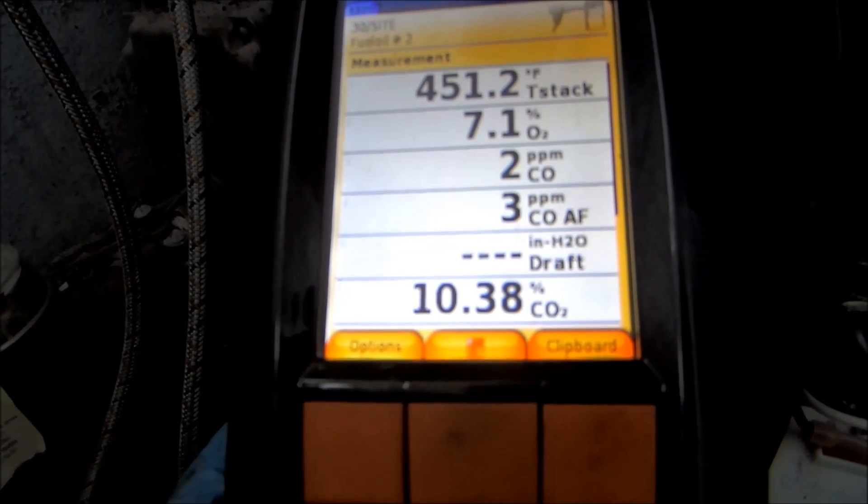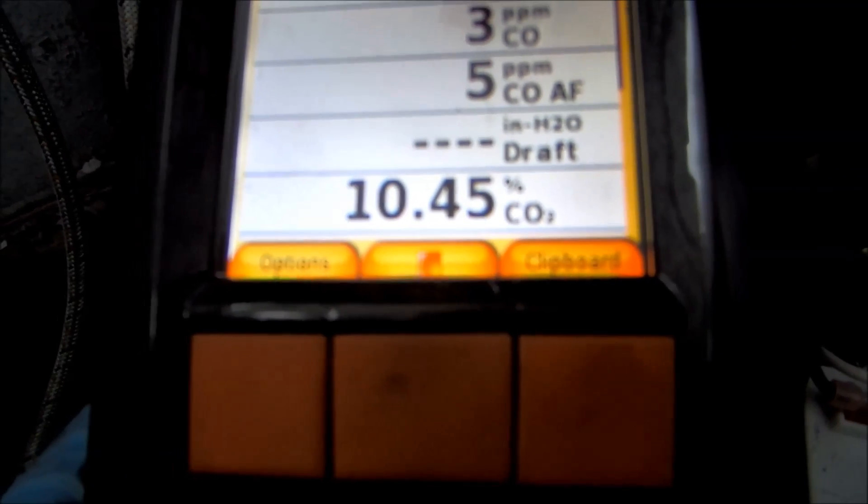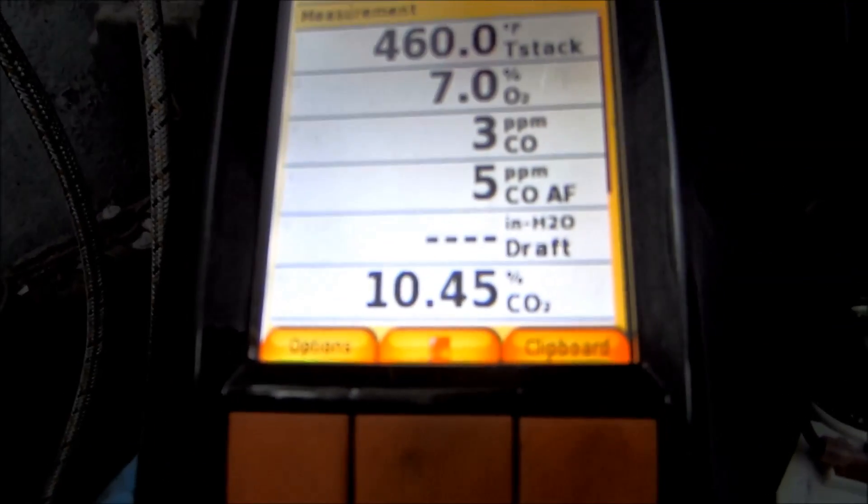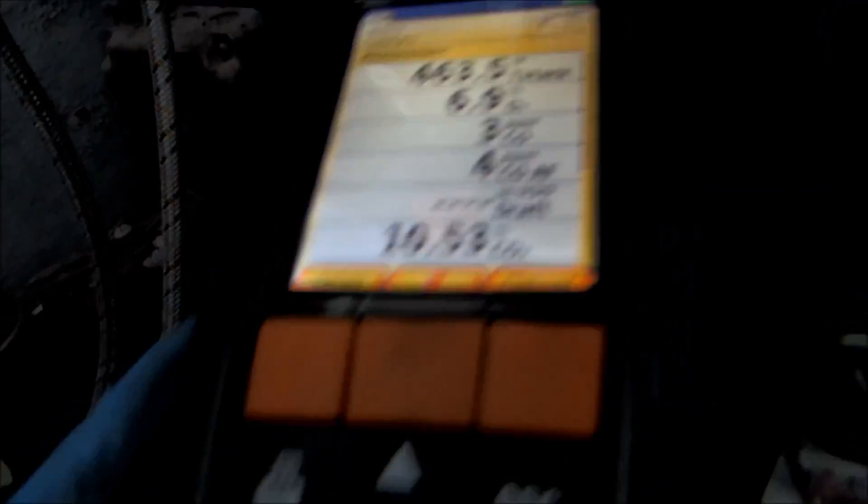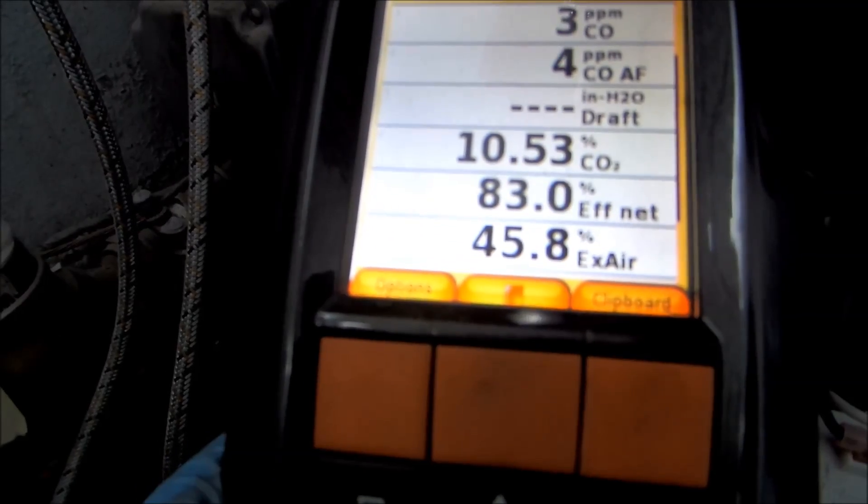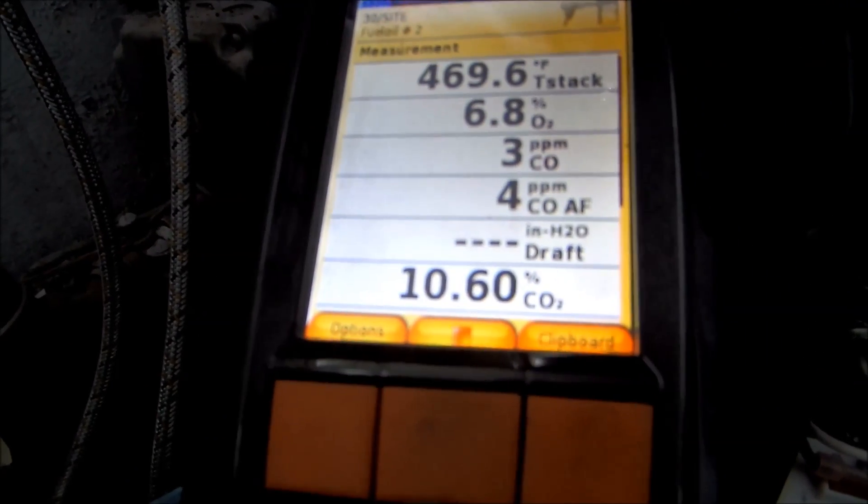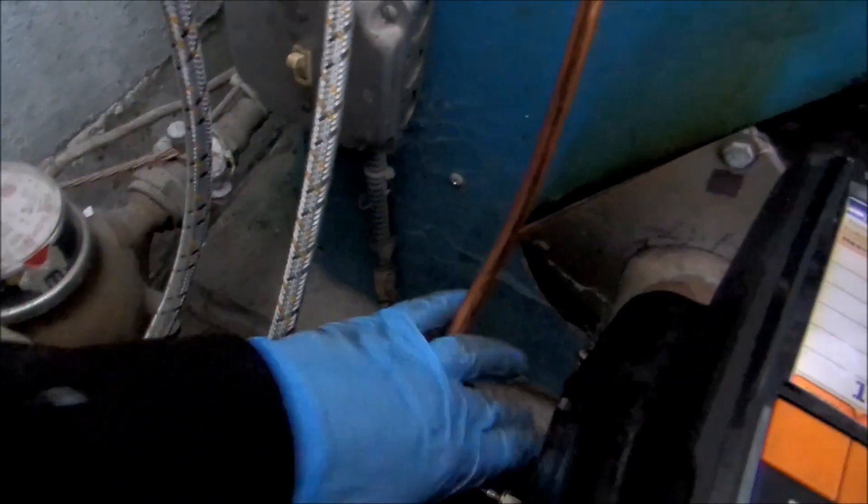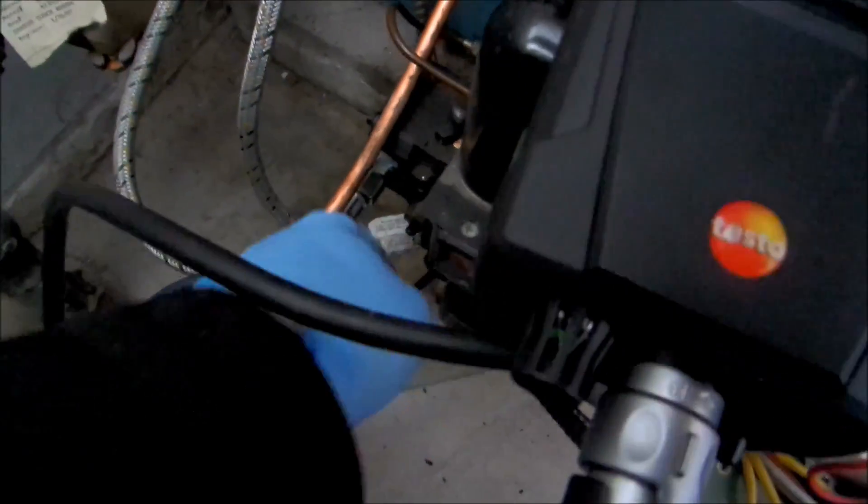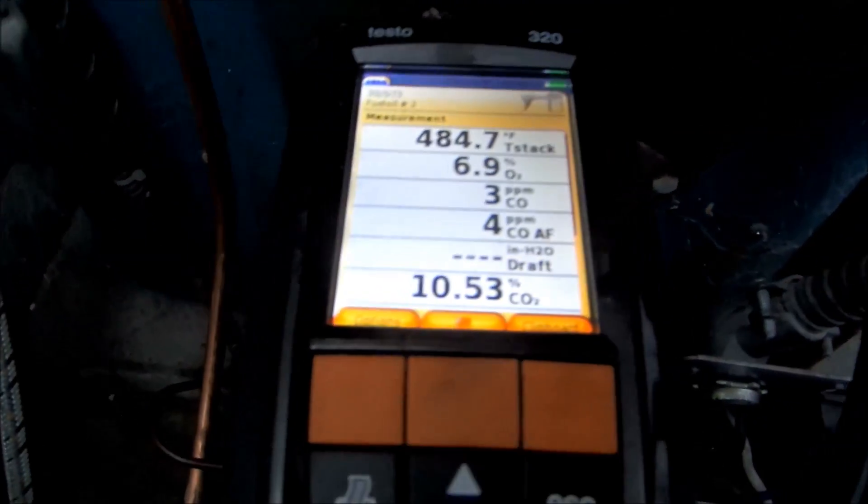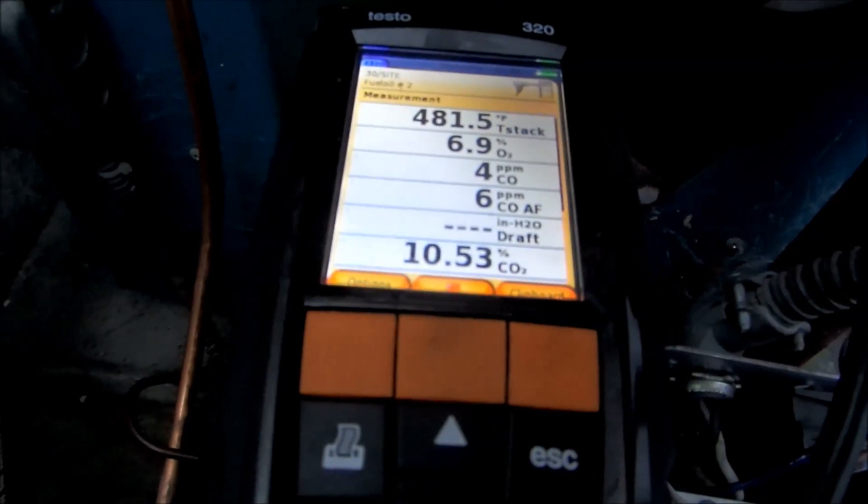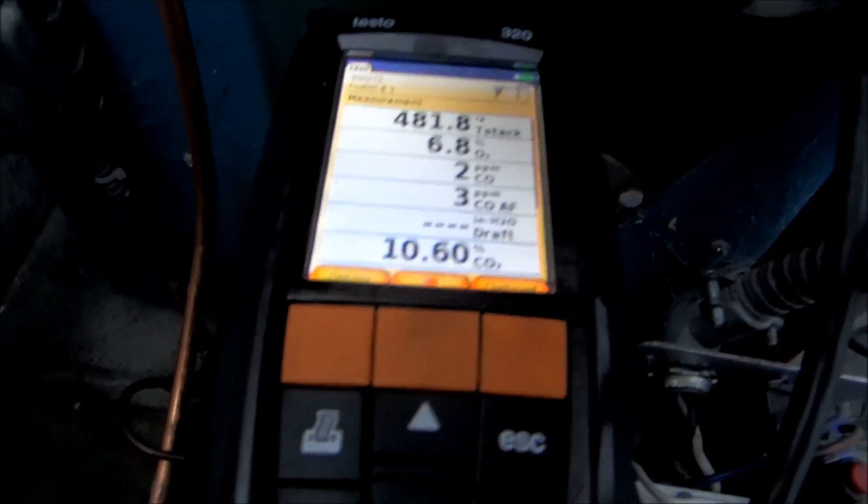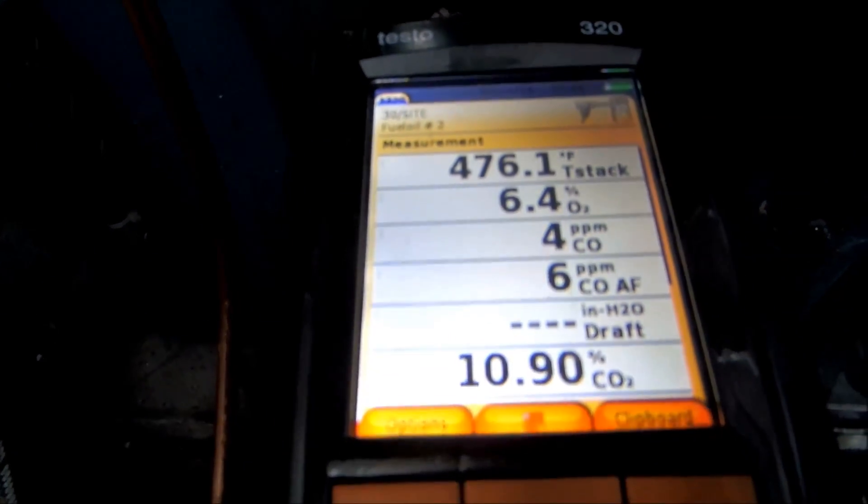I'm going to be able to cut the air band back a little bit and bring that 10.45 up just a little bit. See where my excess air is right now. 45, a little high in excess air. Let me cut that back and see what happens. I'm going to cut the air band back a little bit.